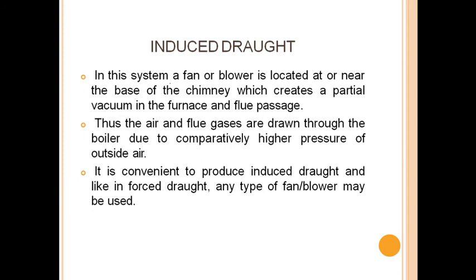In induced draught, a fan or blower is located at or near the base of the chimney, which creates a partial vacuum in the furnace and the flue passages. Thus, the air and flue gases are drawn through the boiler due to the comparatively higher pressure of the outside air. It is very convenient to produce induced draught, and like in forced draught, any type of fan or blower may be used.